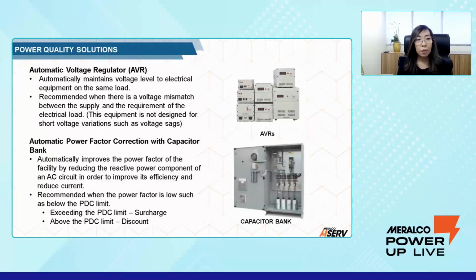And then we also have a cap bank. If your PF or your power factor is below 85, you might want to look at installing a capacitor bank, which can automatically improve your power factor and reduce the reactive power component of your AC circuit. So at Meralco, they actually charge you if you exceed the PDC limit. So it actually pays for itself over time. So these are the things that we can also finance if the requirement is big enough.